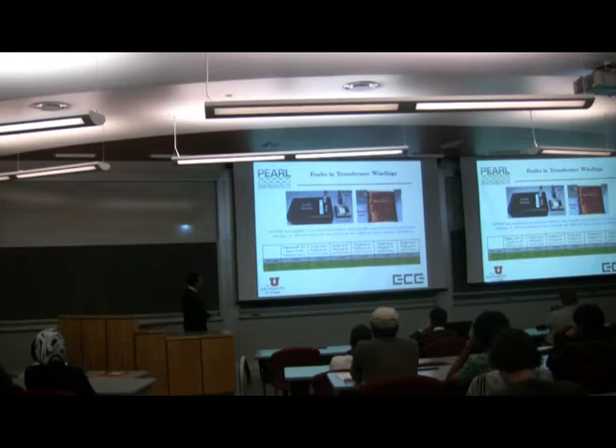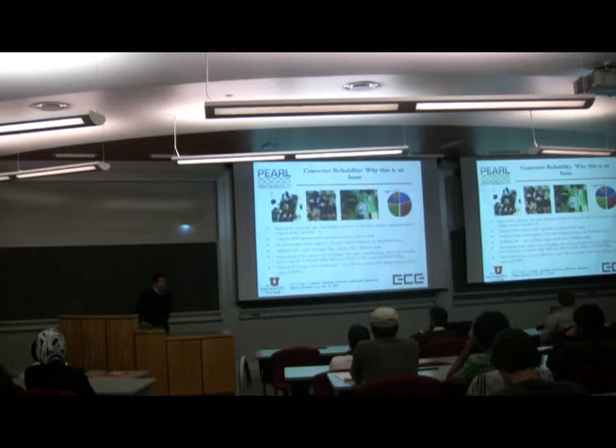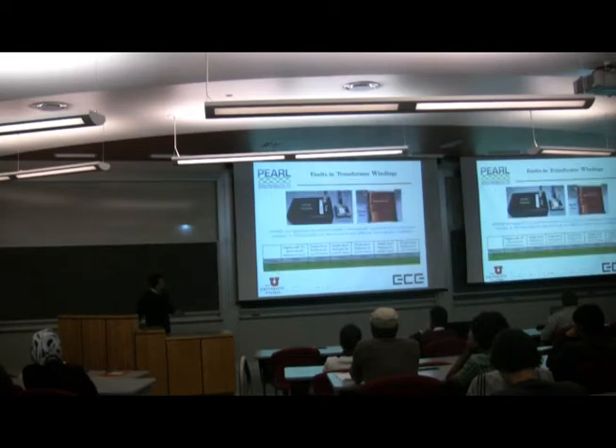And you can see all these reflections will be very different from a healthy and normal transformer, which means that if there is any short circuit, regardless of the location, regardless of where it happened, and regardless of how many windings they are apart, the SSTDR system can detect it. But we have not finished with this experimental analysis.